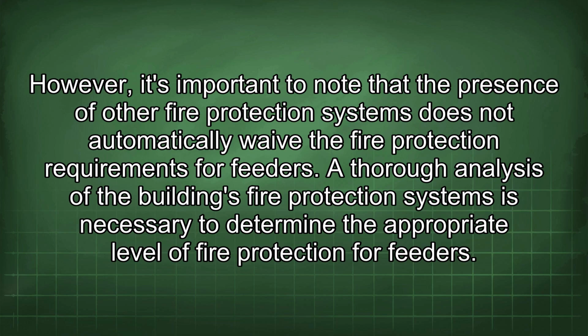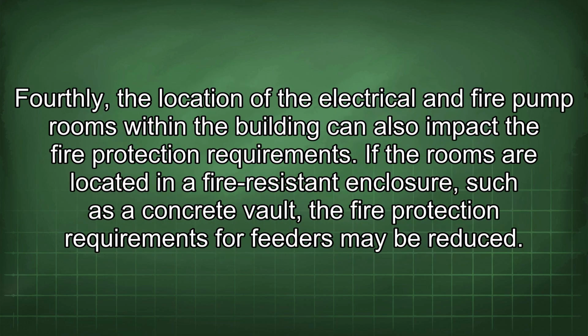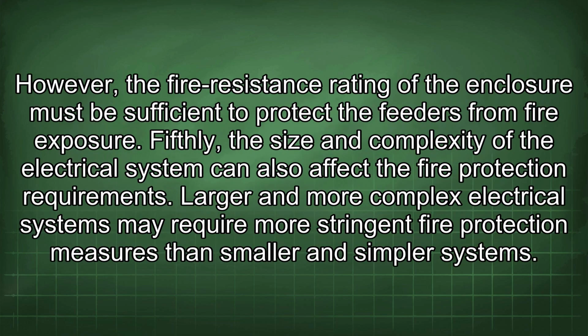fire protection for feeders. Fourthly, the location of the electrical and fire pump rooms within the building can also impact the fire protection requirements. If the rooms are located in a fire-resistant enclosure, such as a concrete vault, the fire protection requirements for feeders may be reduced. However, the fire resistance rating of the enclosure must be sufficient to protect the feeders from fire exposure.